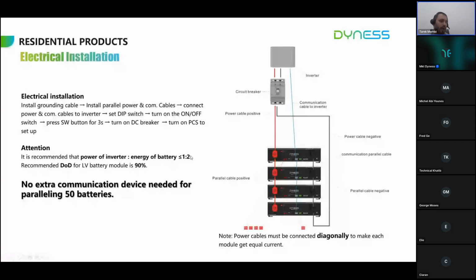Also, I want to add a note that we have an advantage in this product. With many other manufacturers, when the system goes beyond 10 or 20 pieces, it will need extra devices for communication. For this model, no extra communication device is needed for paralleling 50 batteries. So even if the system is big, more than 5 racks, there is no need for any extra communication. Only the master battery should be connected to the master inverter. This is a big advantage and will save us some cost in installations.